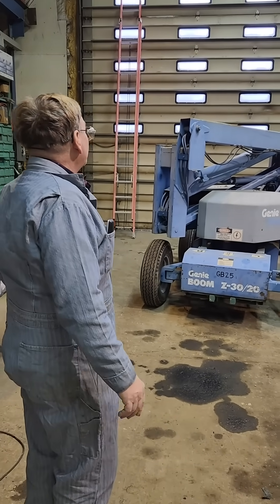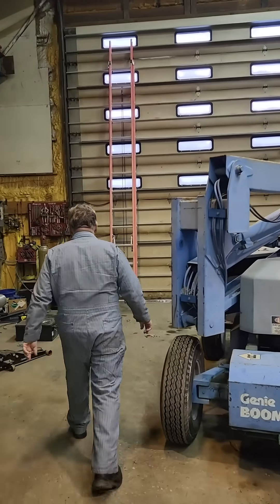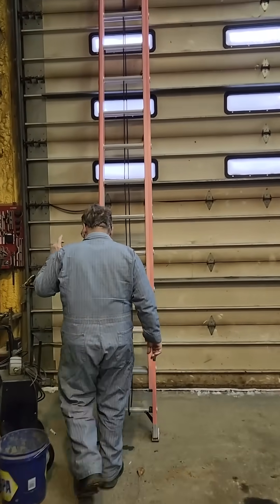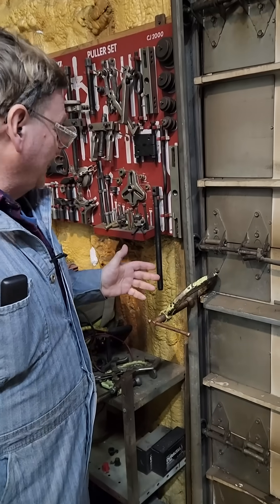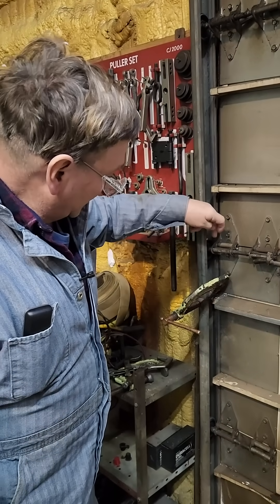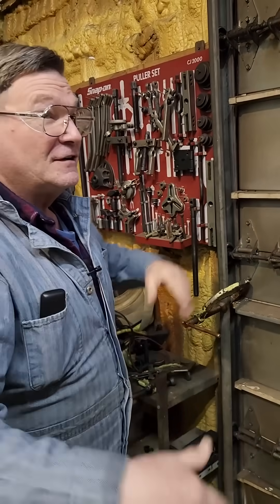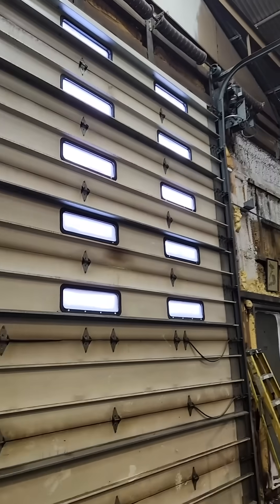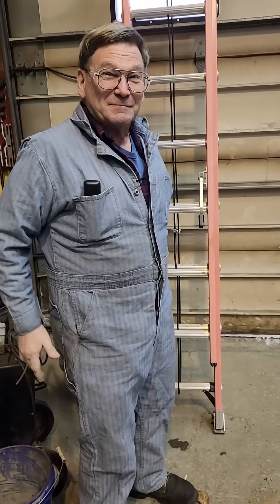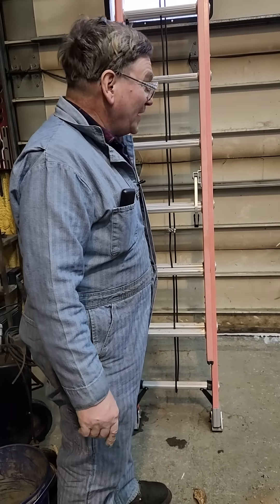In the cold Arctic, you have overhead door things to deal with. We're straightening out this track right now — we just put in a couple new bolts and got it lined up. The jumping caused a roller issue: when one part came loose, it stopped, the roller hung up the door, and you have cables and problems. Because of that, our opener is going to have to be readjusted because it overran and was actually skipping the sprocket — which is good, that's better than stripping things out. So the sprocket skipped and we'll readjust the stops and that should all work fine.